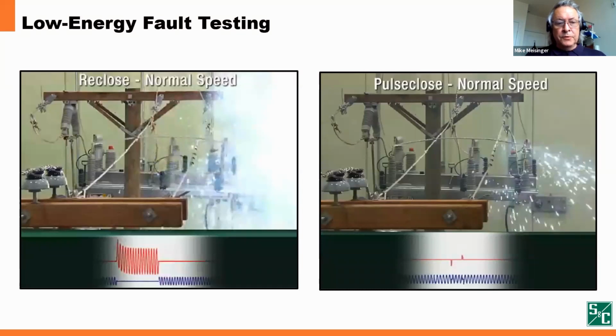So Kleber showed you the consequences of using conventional reclosing, where we're applying 100% of the available fault energy to determine whether that fault is still present. Again, this is a phase-to-phase fault. You can see the conductor laying in between the two phases. And what I would like you to take a look at, there are some jumpers leading up to the conductors, and I'd like you to watch them as Kleber runs that video again. Go ahead and run that video, please, Kleber.